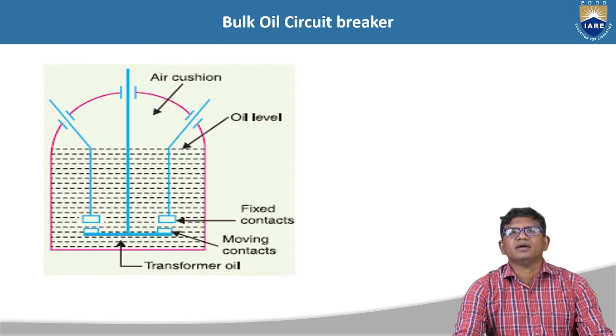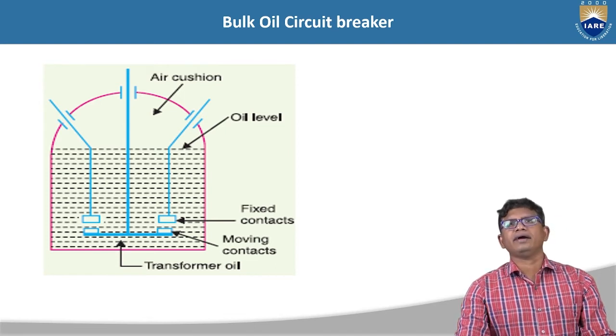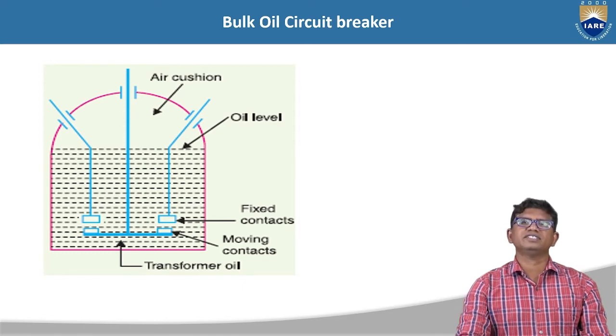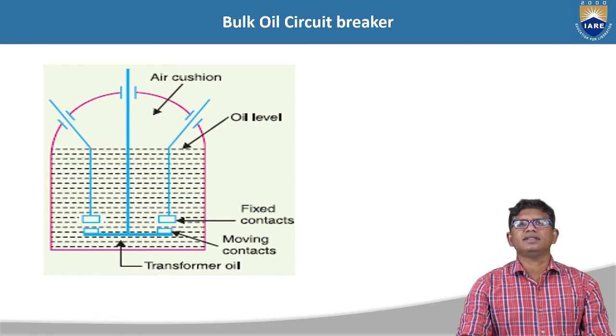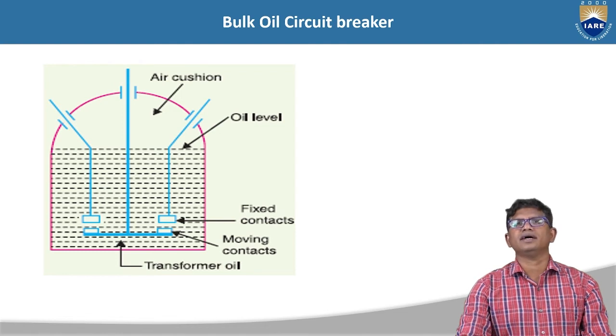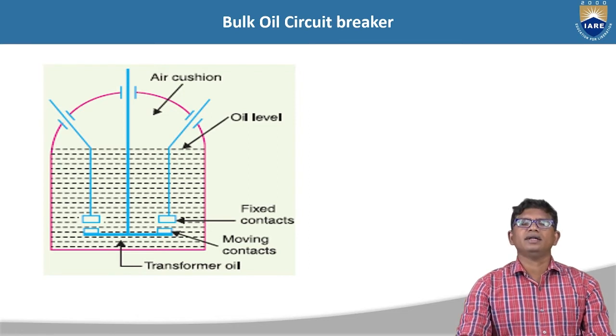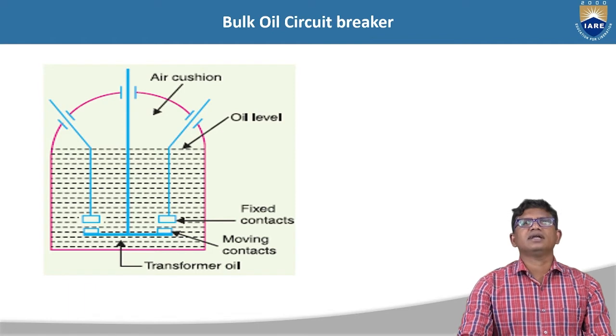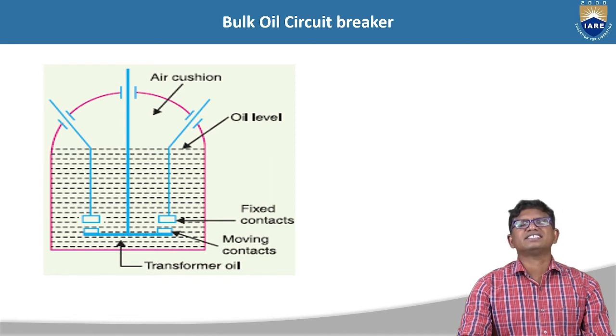The bulk oil circuit breaker is a tank consisting of fixed contact and moving contact. The tank is almost completely filled with oil. At the top of the tank, there is an air cushion above the oil level. The air cushion provides sufficient room for the gases generated during the operation of the circuit breaker.